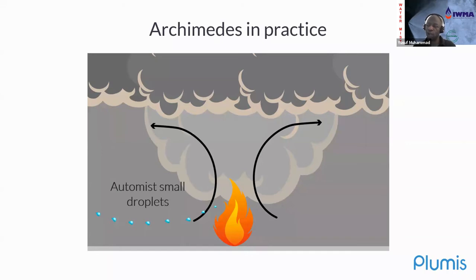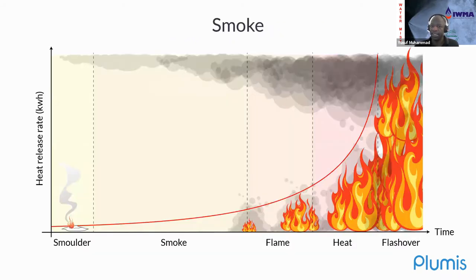So as that fire tries to grow, those mist particles get entrained into its natural turbulence, turn to steam, and you get that powerful suppression and even extinguishment sometimes, depending on the fire load, taking place. There's this difference in principles between water mist and traditional sprinklers that we are trying to make the best use of. The other thing that is different with our approach is how we initiate activation.